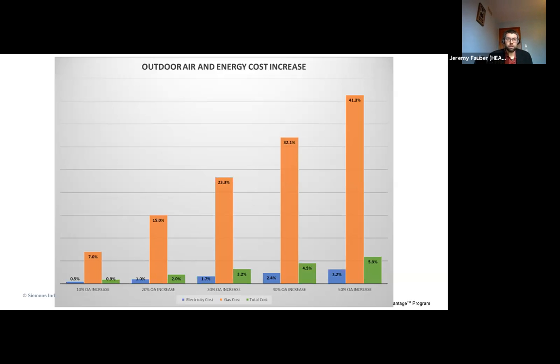If we look at the building breakdown, the reason the green ends up so much smaller is partly because of that difference in cost between gas and electric, and partly because in our models, heating just doesn't get used as much as electricity. I think in real life that ends up being a little less skewed, and there's a little bit more gas cost typically experienced. But just as a reminder, these numbers in terms of cost are going to shift based on the efficiency of your equipment. If you've paid to put more efficient equipment in, it can deal with those increased energy requirements more cost effectively than if you didn't.